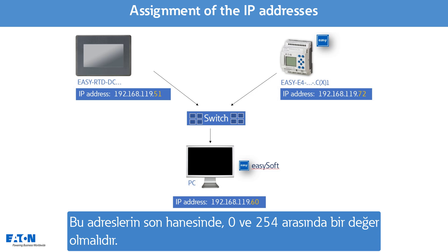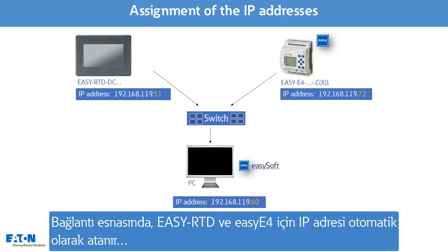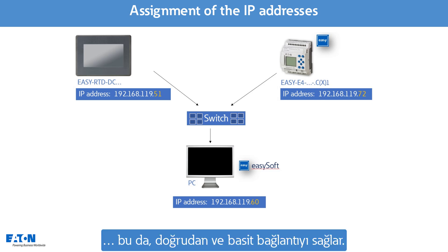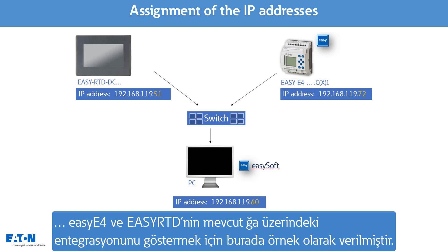The last digit can be set between 0 and 255. For the EASY-RTD, the end address 51 is selected here. A brief note: the EASY-RTD and the EASY-E4 are set to Auto-IP when delivered, which enables a direct, simple connection. The variant with a fixed IP address is shown here in order to demonstrate the integration of the EASY-E4 and the EASY-RTD in an existing network.